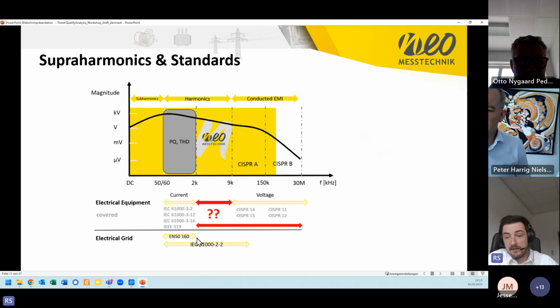Due to nonlinear power generation and nonlinear loads in the grid, we see on one hand DC components and subharmonics, the frequency spectrum below 50/60 hertz. But because of the more efficient IGBT and MOSFET technologies, we also see emissions in higher frequency components, up to 150 kilohertz or even more.